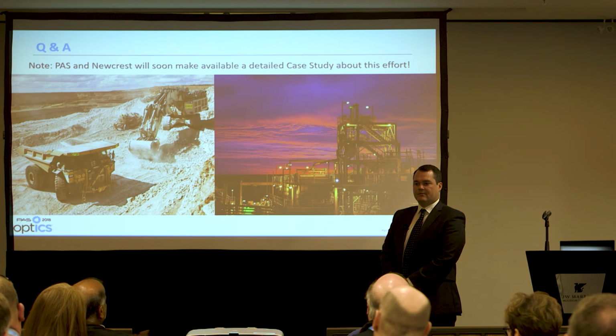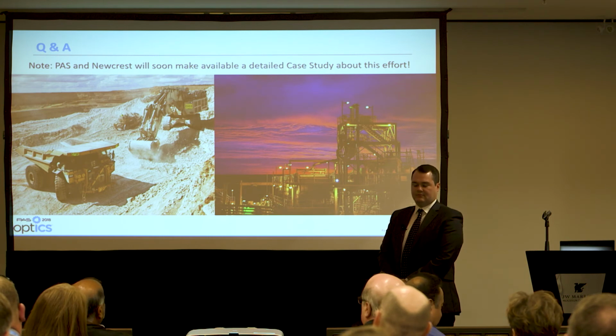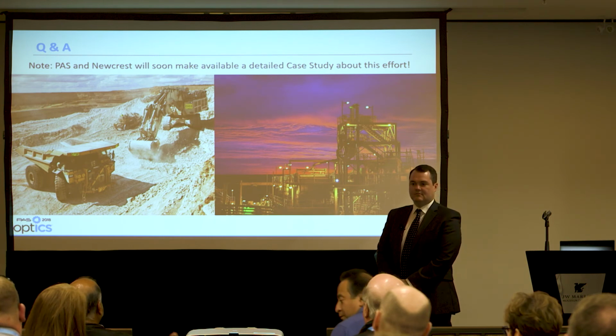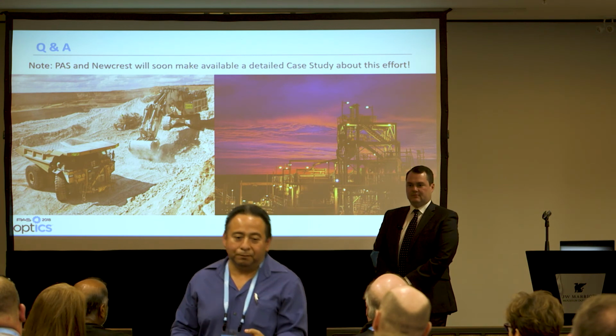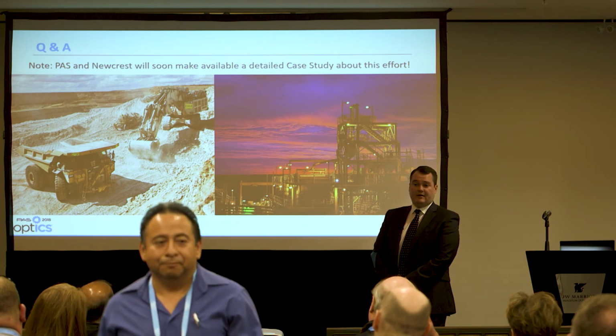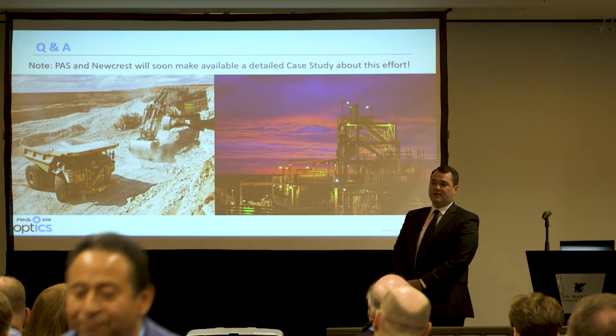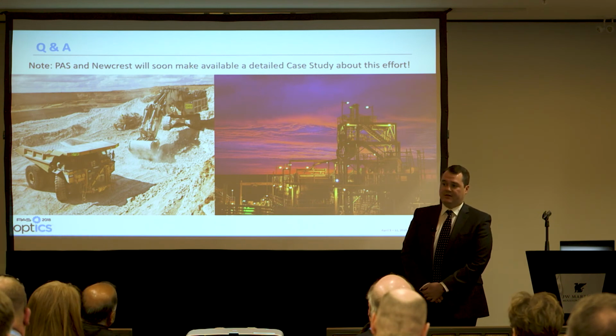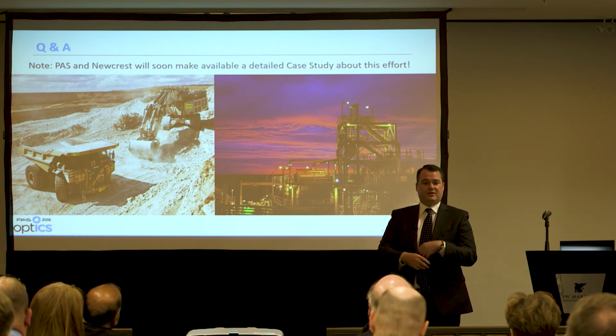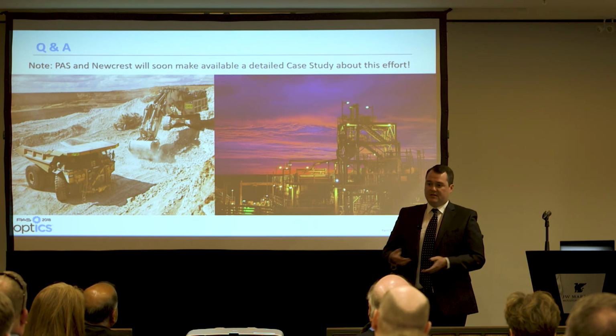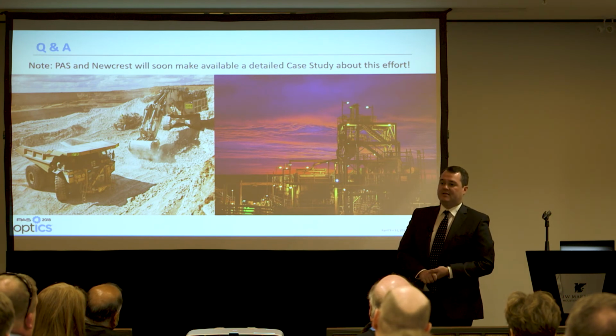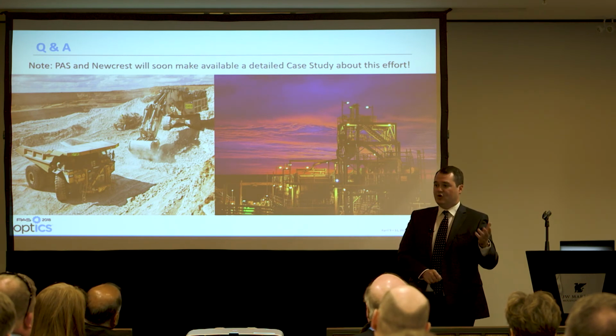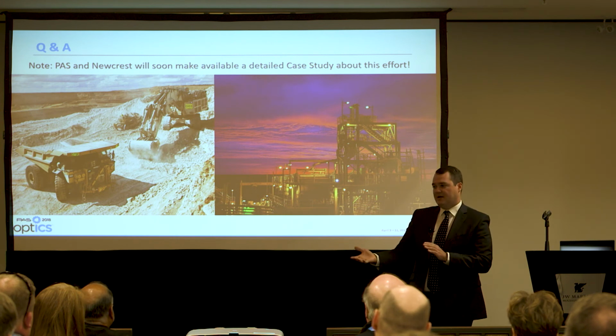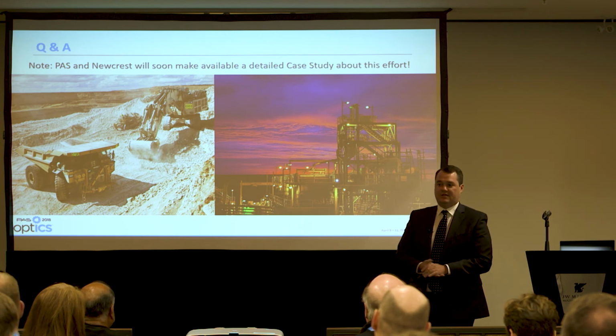Some of the pumps or motors, when you're starting, suppress those alarms for a minute to let things like flow or pressure settle down. Yeah, that's exactly right, and that was key to us sustaining those alarm rates through shutdowns. Typically you'll have a shutdown or your equipment goes off and you'll get a huge flood of alarms, so we use exactly what you're talking about - state-based alarming. If the equipment's isolated and the control power's off, it will suppress the alarm, so we can now sustain through shutdowns with low alarms.